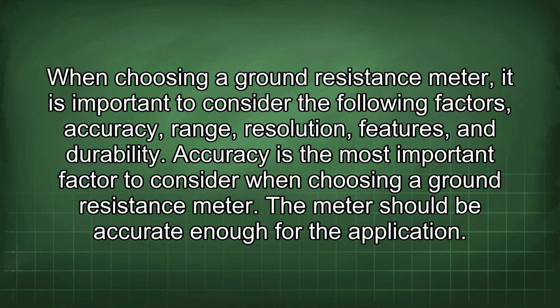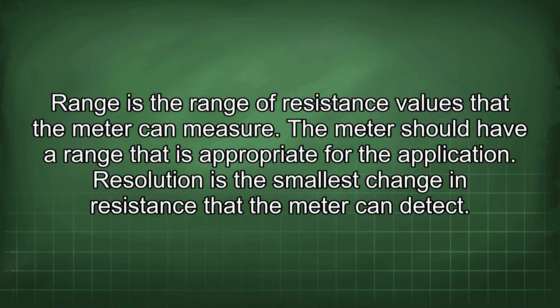When choosing a ground resistance meter, it is important to consider the following factors: accuracy, range, resolution, features, and durability. Accuracy is the most important factor to consider when choosing a ground resistance meter. The meter should be accurate enough for the application. Range is the range of resistance values that the meter can measure. The meter should have a range that is appropriate for the application. Resolution is the smallest change in resistance that the meter can detect.